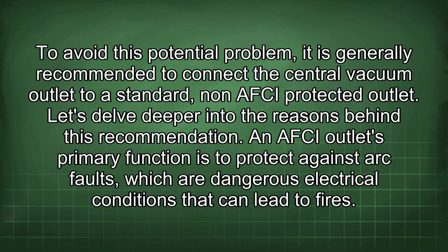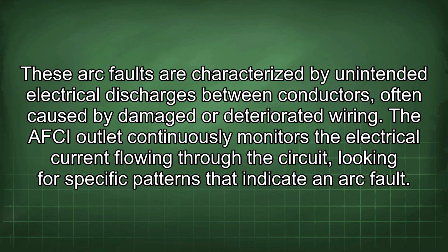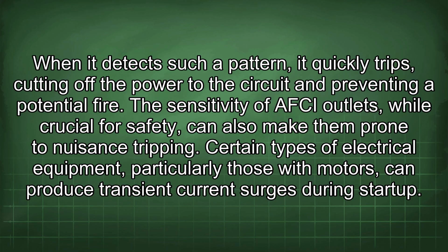To avoid this potential problem, it is generally recommended to connect the central vacuum outlet to a standard, non-AFCI protected outlet. Let's delve deeper into the reasons behind this recommendation. An AFCI outlet's primary function is to protect against arc faults, which are dangerous electrical conditions that can lead to fires. These arc faults are characterized by unintended electrical discharges between conductors, often caused by damaged or deteriorated wiring. The AFCI outlet continuously monitors the electrical current flowing through the circuit, looking for specific patterns that indicate an arc fault.